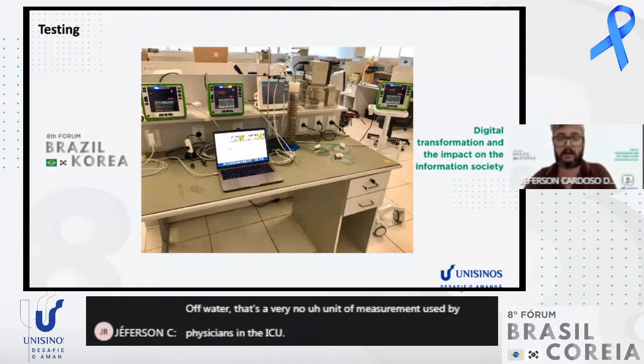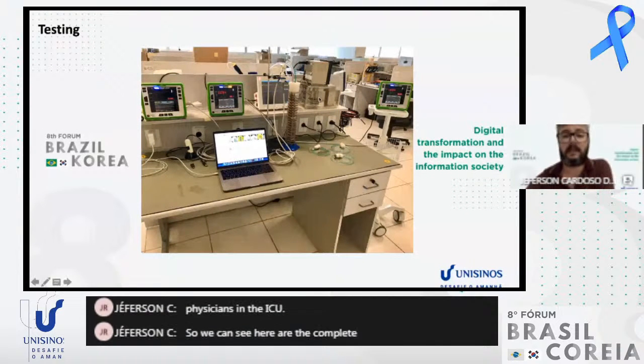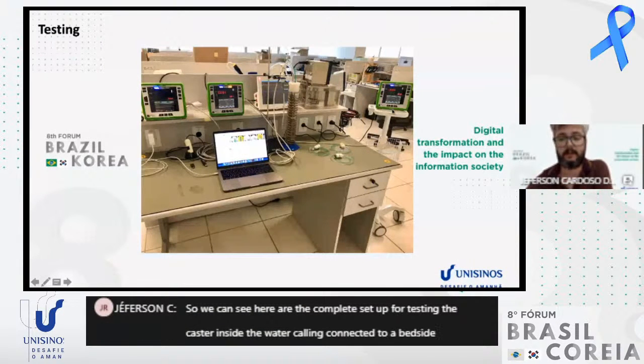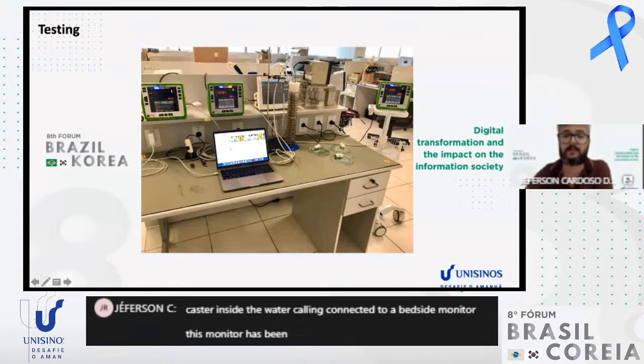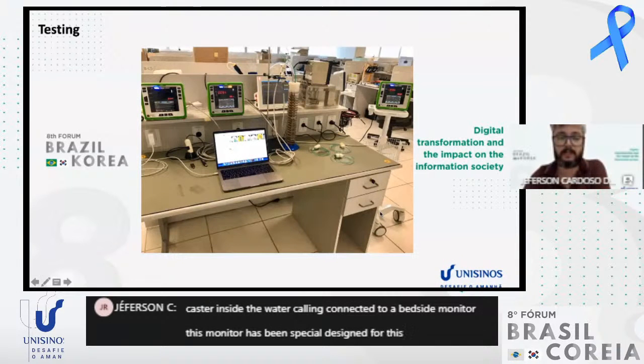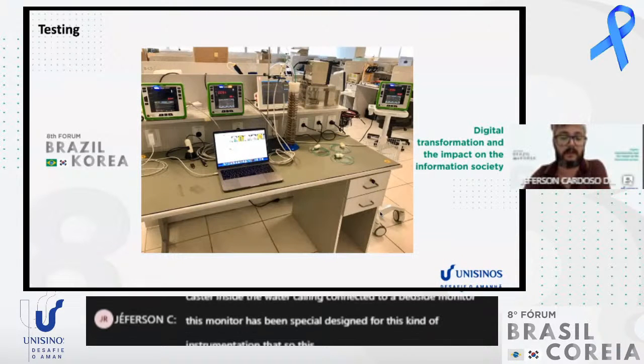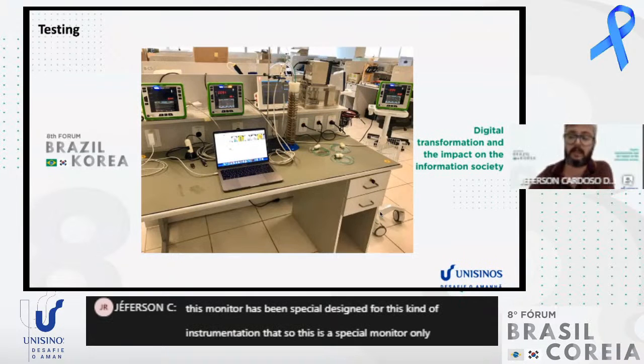So we can see here the complete setup for testing: the catheter inside the water column connected to a bedside monitor. This monitor has been specially designed for this kind of instrumentation, a special monitor only for ICP and brain temperature measurement.